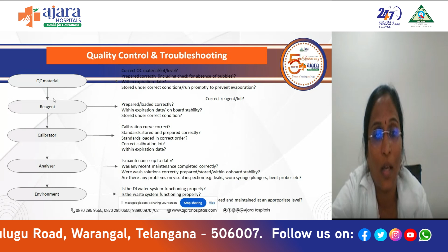So whenever there is a problem, you have to check whether the material is correct or not, whether the control is prepared properly or not. While doing the control, who is doing the pipetting, is there any bubbles during the pipetting, whether the reagent is expired or not. You have to see all that. And coming to reagents, whether they are loaded properly, or do they have an expiry date, whether the stability is okay or lost, and whether they are stored properly. The manufacturer's given temperature should be maintained during reagent storage.